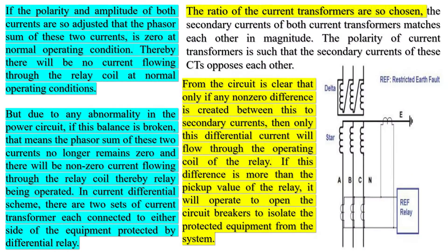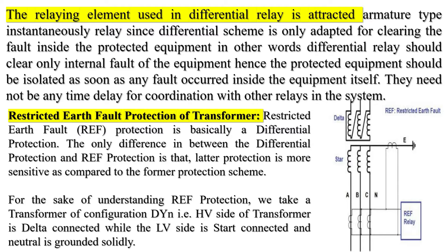Stability tests are performed on transformer differential protection relays and transformer-restricted earth-fault protection relays. These tests serve to verify correct polarities, validate setting calculations, and ensure the ratio and phase angle compensation of the differential protection.